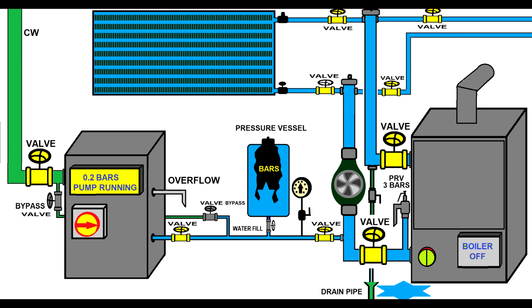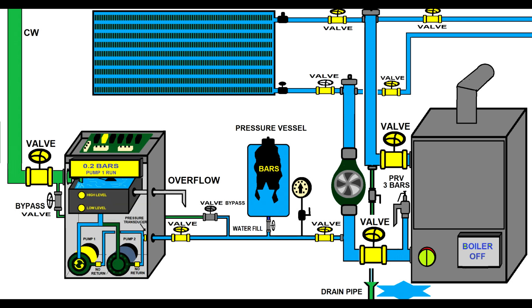This is okay, but in the morning, because you lost too much water, when the heating agent cools down, you have only 0.2 bars in the installation, and the pump will run to compensate for the heating agent that you lost. And that's okay, but then you will really abuse these pumps. They will work every day to compensate for the water you lose, and sometimes you might damage one pump.